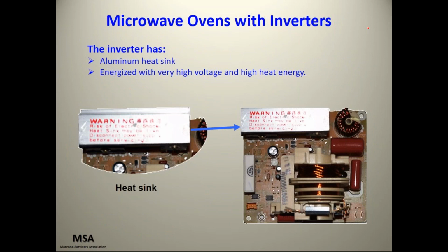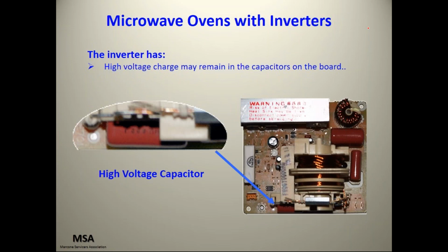The inverter has an aluminum heatsink energized with very high voltage and high heat energy. It's hot in both respects, temperature and voltage. The inverter has a high voltage charge, which may remain in the capacitors on the board. They mention 30 seconds, but just like the capacitor in a regular microwave, don't trust it. Discharge it just to be on the safe side before you work on this thing.